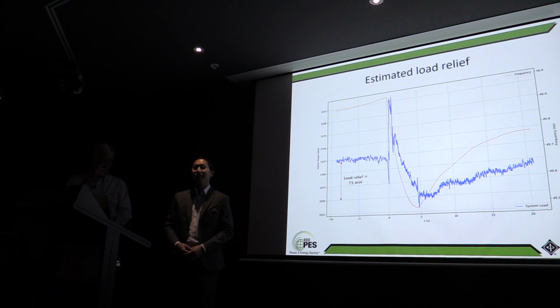Certainly, there's logic in that, and they're brilliant for that because they have very low windage. You mentioned friction. They don't have much friction because they're hydrogen cooled. So you just leave the hydrogen cooling system on and you've got a nice free-running, low-loss system. And if you want to put in VAR control like STATCOMs or SVCs, you don't get any contribution to system strength, but you do with a synchronous condenser. So it's actually a good plan to do it. I hope Synergy really take that one up.